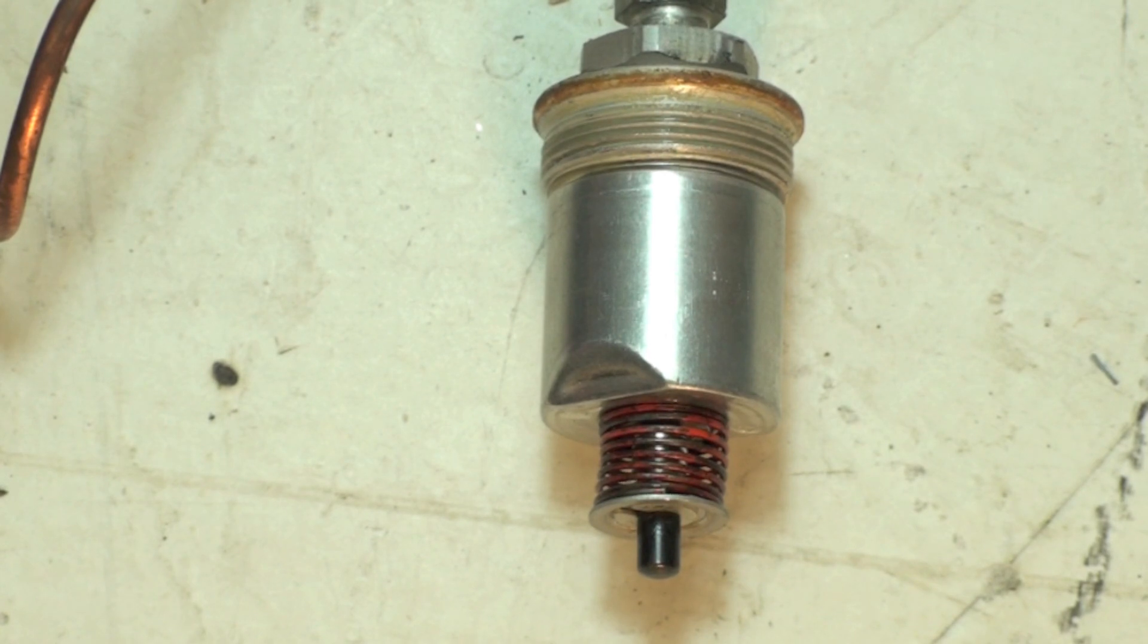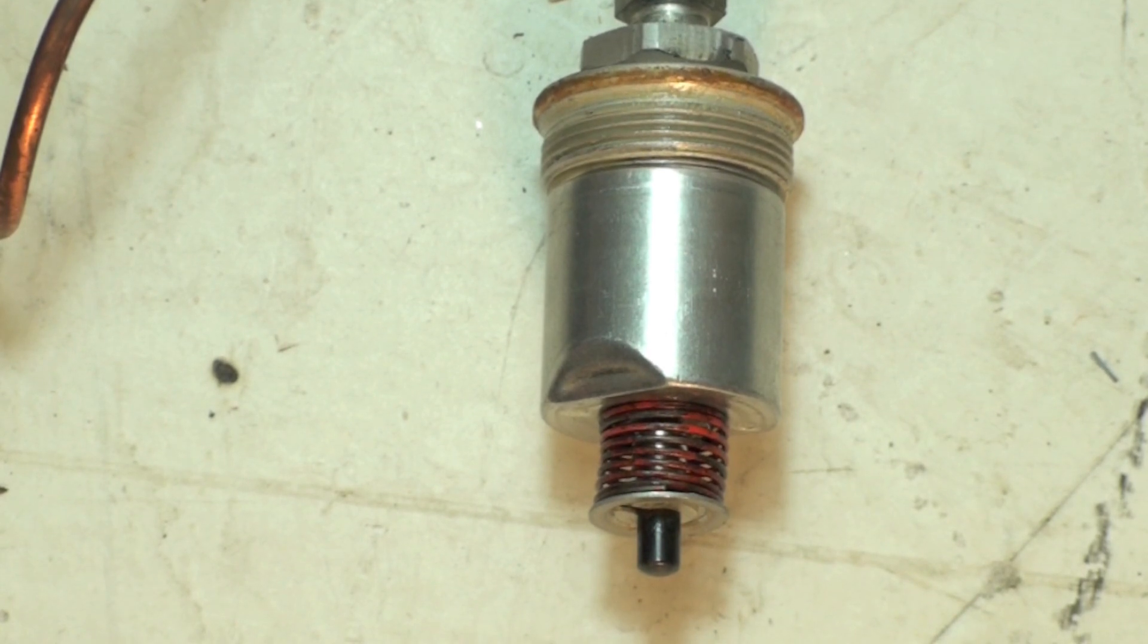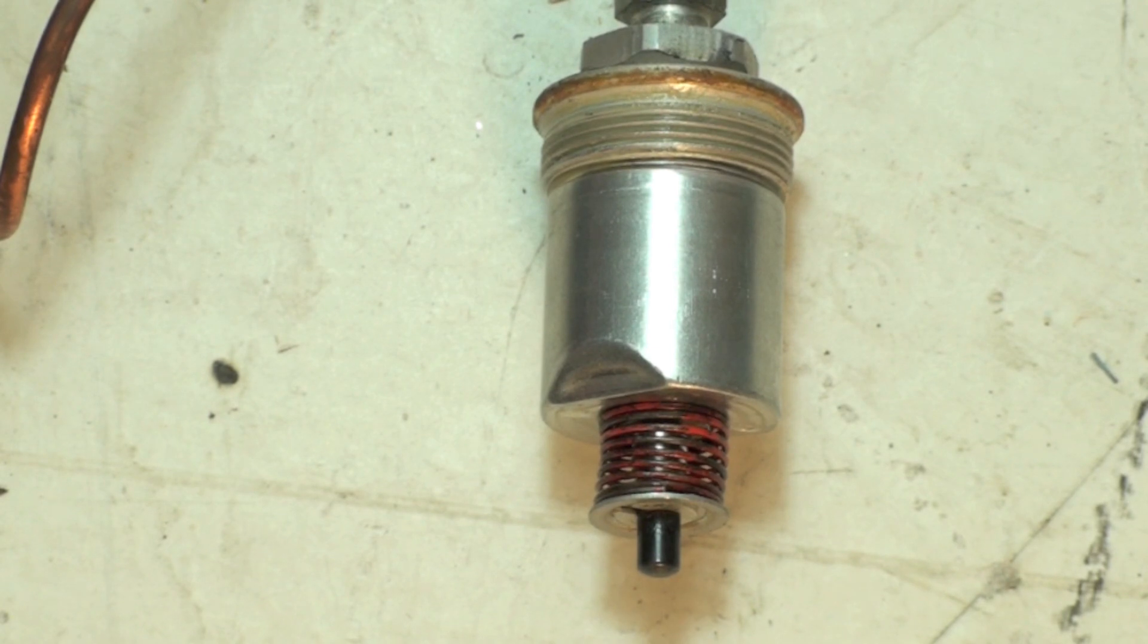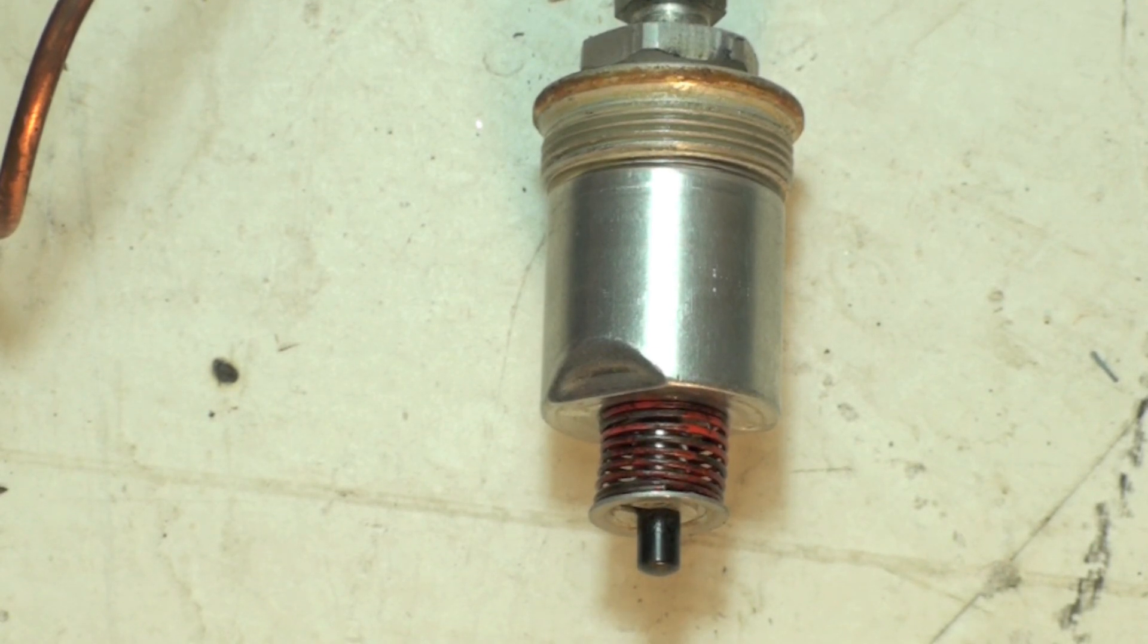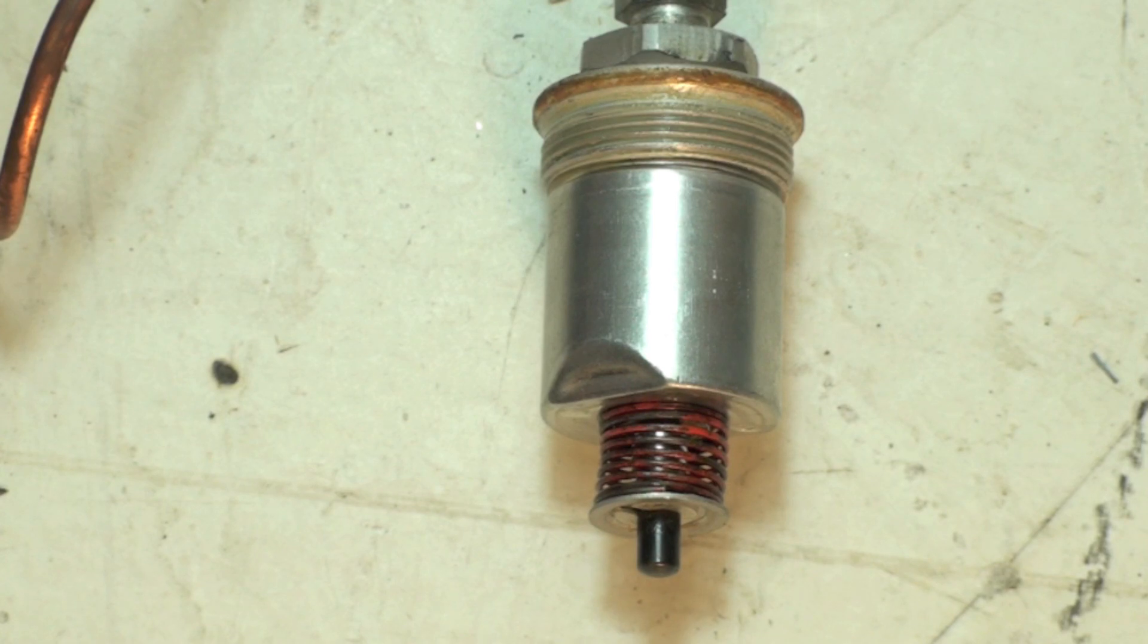They usually drop out in about a minute and a half or something like that. If they drop out in like 10 seconds, there's something wrong. You're not getting enough power from the thermocouple, the solenoid's going bad, something like that.